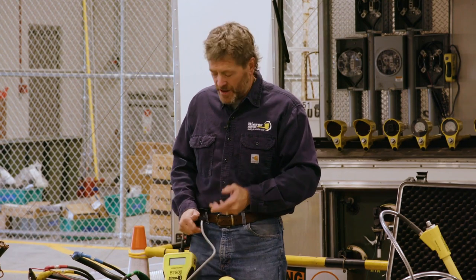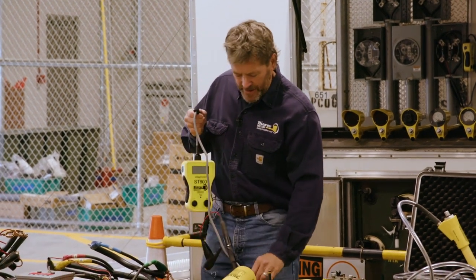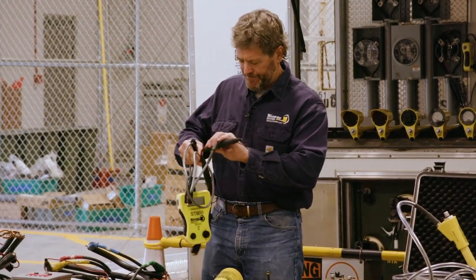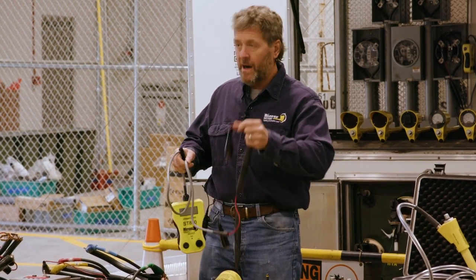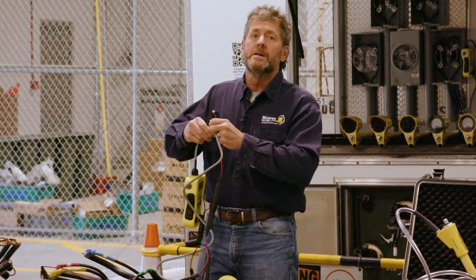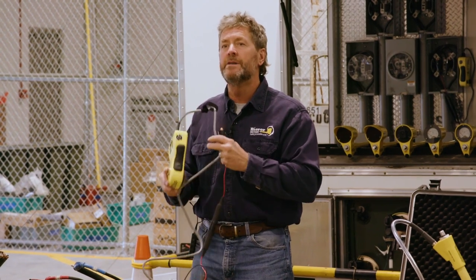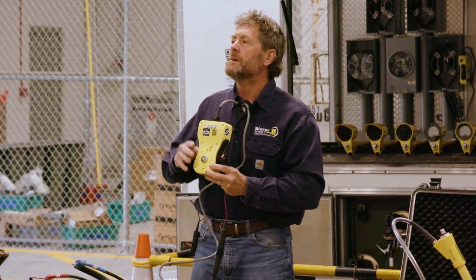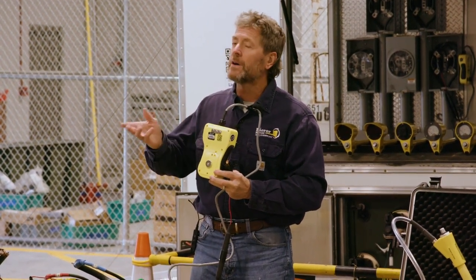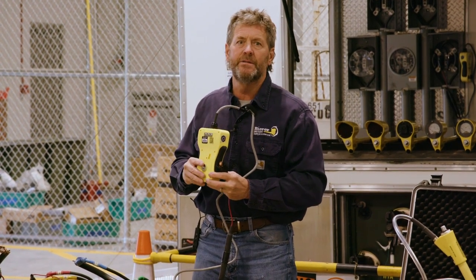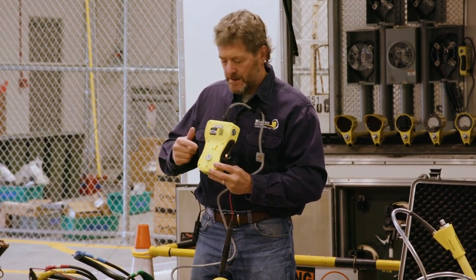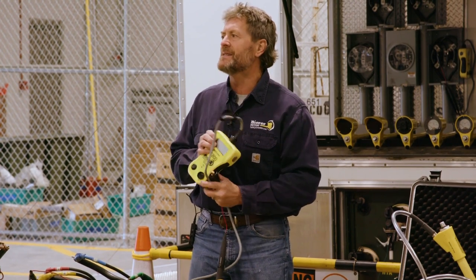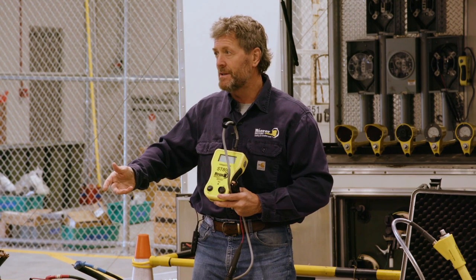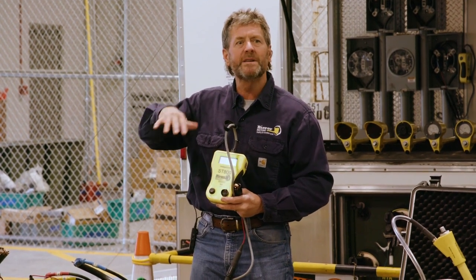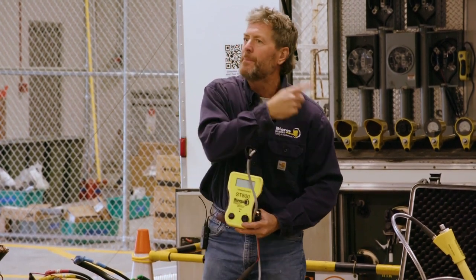So you're gonna turn the tool off, take your red lead and go to hot leg two. Turn the tool back on, look at the voltage. Well, we're seeing 100 volts again, so now the common denominator is you've got a neutral issue. Turn it on, go up to the load, and you expect to see slow counts. And you expect, because it's the same situation, that it's gonna get up to about 40 amps, fall on its face, recount, and you'll hear popping.